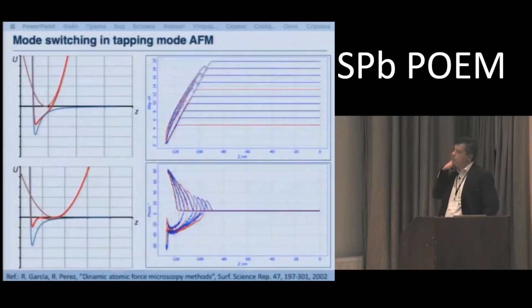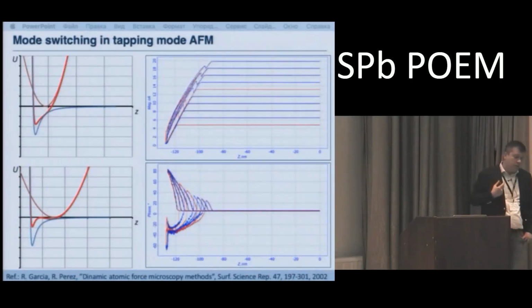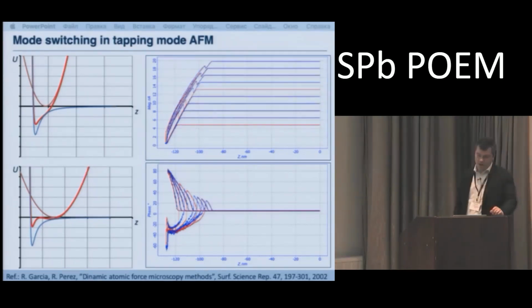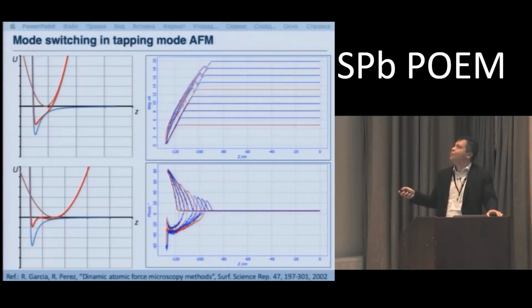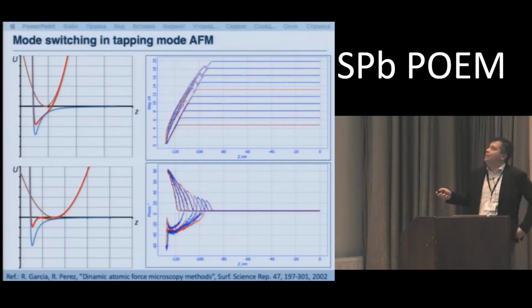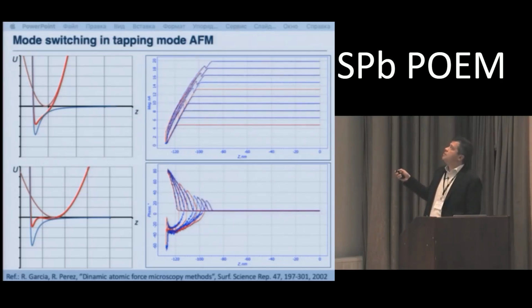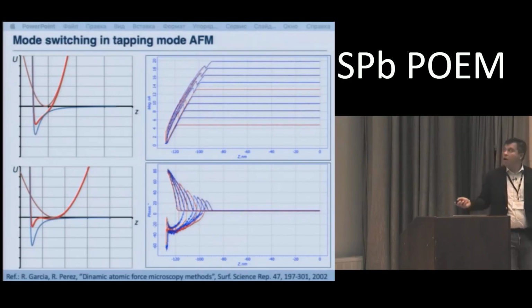So this is the first simple point, but despite being quite simple, there are a lot of published images with artifacts of this kind. The second point is that when we operate in tapping mode, the interaction potential between the cantilever and the sample can be approximated in different ways, but independently of what kind of formula is used, some kind of curve like this blue curve will be plotted. So in this system, it is possible for the cantilever to jump from the attraction regime to the repulsive regime, and this is the dependence of the cantilever amplitude on the distance between the cantilever and the sample at different free amplitudes. The smaller the amplitude, the closer to the surface the jump from attraction to repulsion will occur.